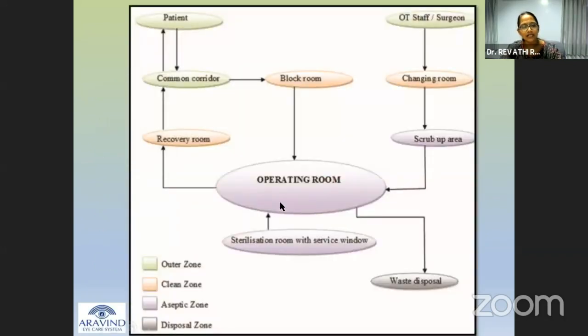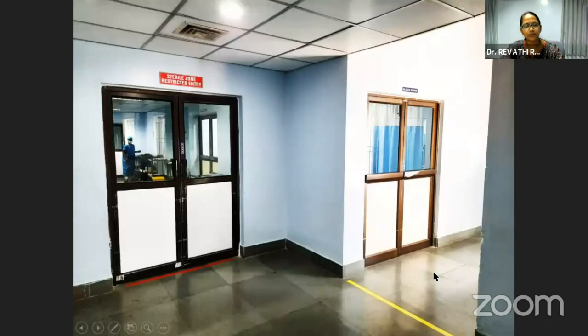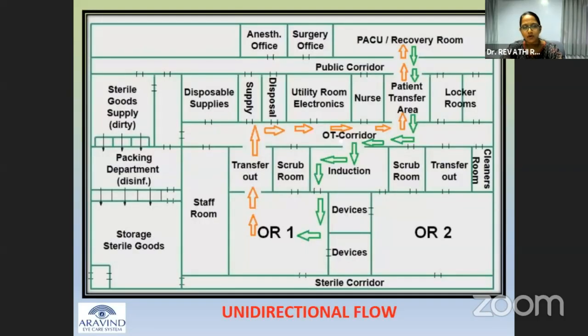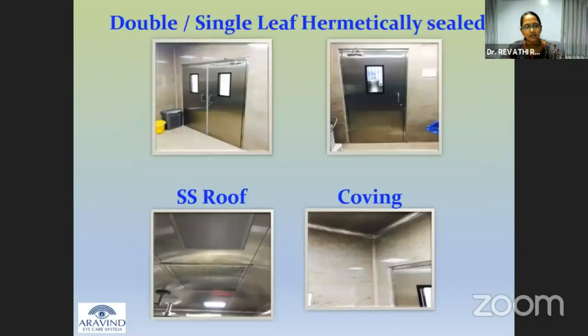Always maintain a unidirectional flow. Here it is clearly shown in the picture how the patient flow is towards the operating room, how the staff flow is towards the operating room, how the sterilization window is present, and how the materials exit for waste disposal. So specific color codings and specific denotations about the area and the sterile zone have to be displayed in the operating theater. So unidirectional flow has to be kept in mind when we design our theaters.